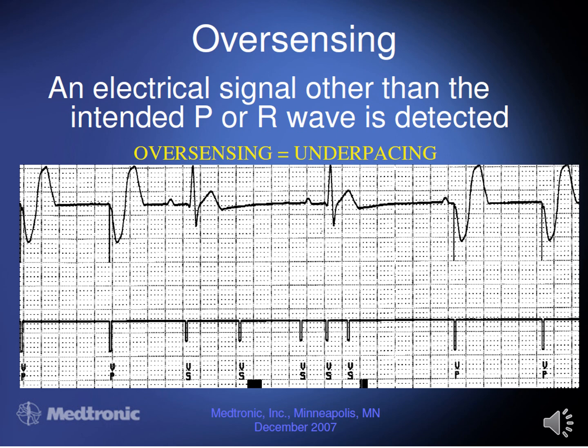Okay, this next slide talks about oversensing. This is something we don't see as much, but it is important for you to know about. Basically, the pacemaker thinks something else is the patient's own intrinsic heartbeat. Maybe the patient has hiccups, burping, or something else like that, and the pacemaker says, oh, I don't have to do anything. When you look at this slide, you see the paced beats, and then a sinus beat, and then between those two sinus beats there's quite a long pause. There should really be a paced beat somewhere in there. So the pacemaker is seeing way too much, and you want to limit what it sees. You raise the fence so it is more selective on what it sees.